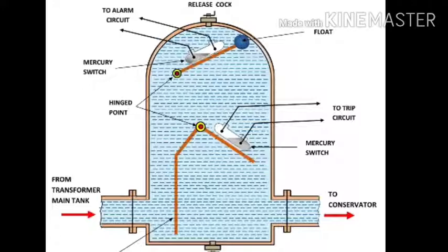The advantages of the Buchholz relay: it indicates internal faults due to heating and helps avoid a major fault. The second advantage is that the severity of the fault can be determined without even dismantling the transformer. If a major fault occurs in the transformer, it can be isolated with the help of the Buchholz relay to prevent an accident.